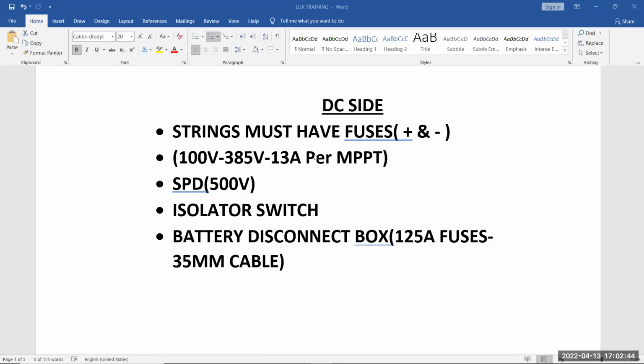So positive and negative fuses, SPD as well. On this system, a 500 volt SPD is sufficient for the MPPTs if you run it up to 480 volts. If you have strings that are less than that and you know you're not going to upgrade, you can adapt your SPD to the voltage that you're going to run.